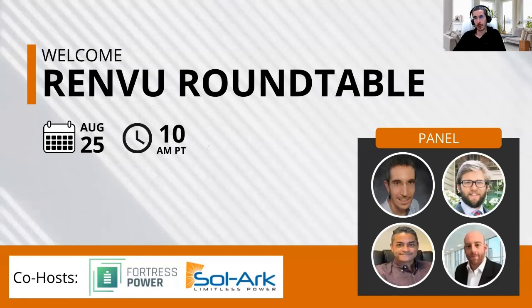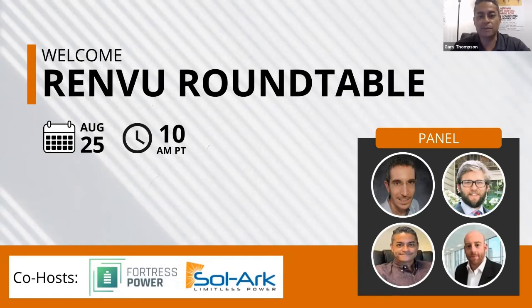Are you planning to come out with a new eVault that can be installed outdoors based on this new requirement? We don't have one currently in development that will work outdoors. As we know, cold weather has more adverse effects on lithium batteries than warm weather. What can be done is use enclosures or sheds to keep the ambient temperature range of the battery between our recommended 32 degrees Fahrenheit and 113 degrees Fahrenheit. Cold weather generally slows charging and discharging, so when units are installed outside, it's important to still follow our recommended charging and discharging practices to fulfill our guaranteed 10-year warranty.